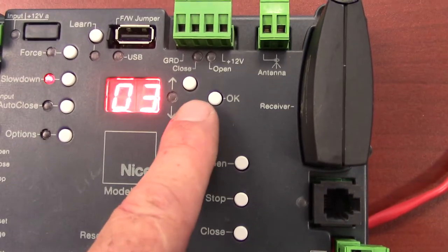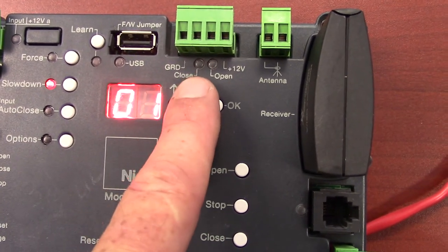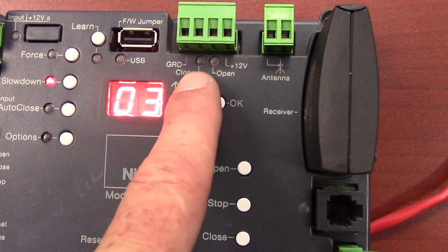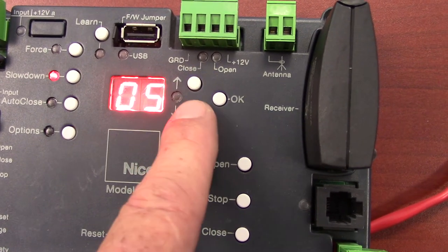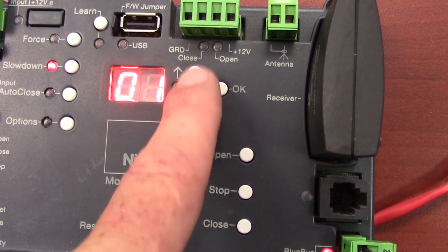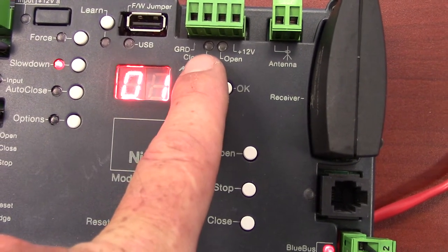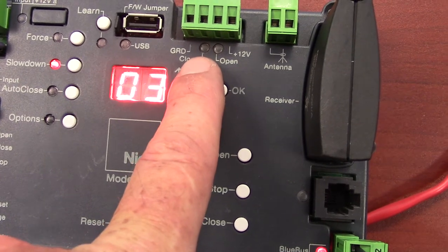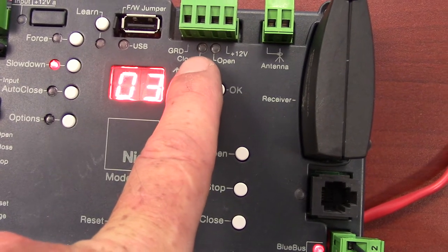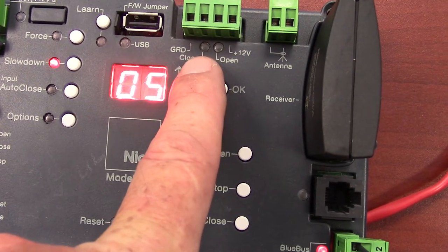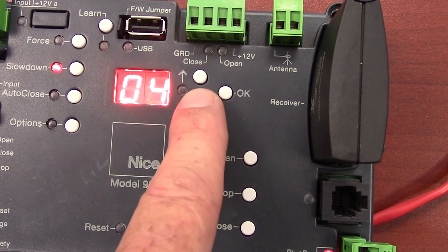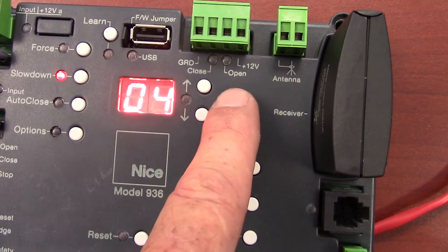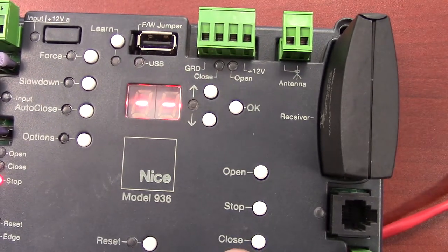We can change that setting to 2, 1, anything between 1 and 5. What this means is that we can slow the operator at 5% from the limit, 10%, 15% which is the default, 20 or 25% before the limit switch. And we just press OK to lock in that value.